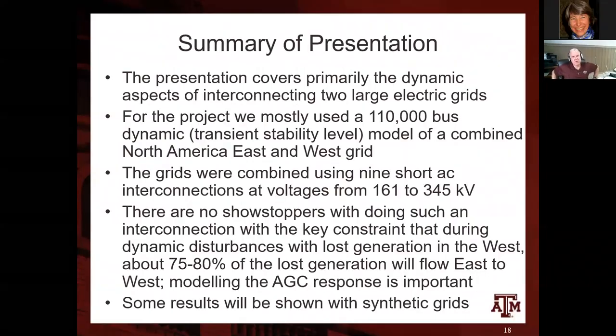So, the summary of the presentation: we took these two large grids and got the best models we could, provided by the different utilities involved. This involved setting up a 110,000 bus dynamic, or transient stability level, model combining the North American Eastern and Western grids. Usually we've got about an 80,000 bus model for the Eastern grid and about a 30,000 bus model for the Western grid, and we put them together.